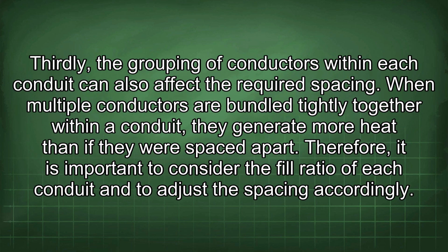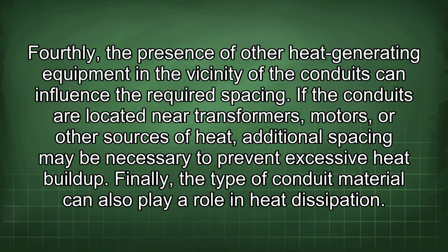Thirdly, the grouping of conductors within each conduit can also affect the required spacing. When multiple conductors are bundled tightly together within a conduit, they generate more heat than if they were spaced apart. Therefore, it is important to consider the fill ratio of each conduit and to adjust the spacing accordingly. Fourthly, the presence of other heat-generating equipment in the vicinity of the conduits can influence the required spacing. If the conduits are located near transformers, motors, or other sources of heat, additional spacing may be necessary to prevent excessive heat buildup.